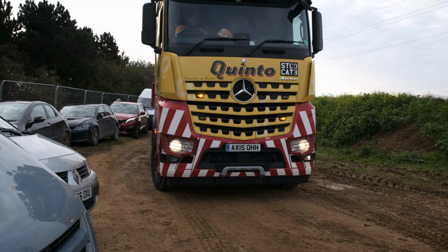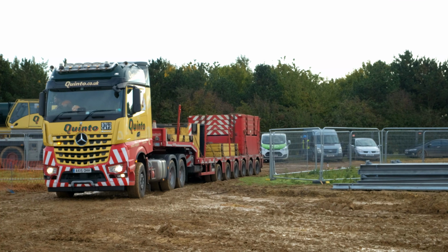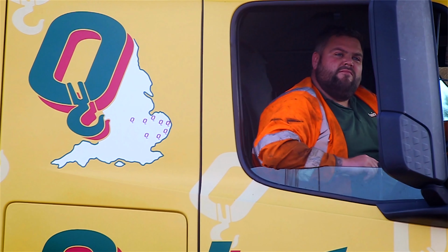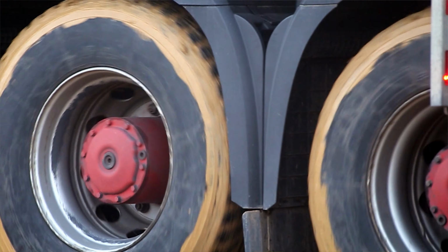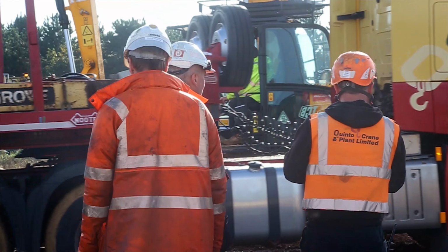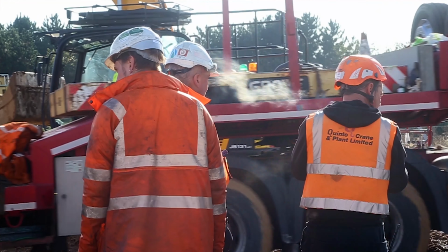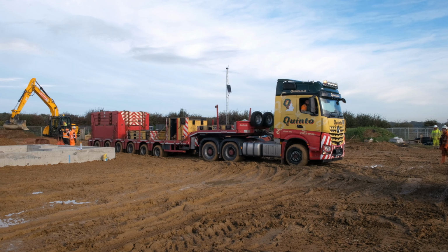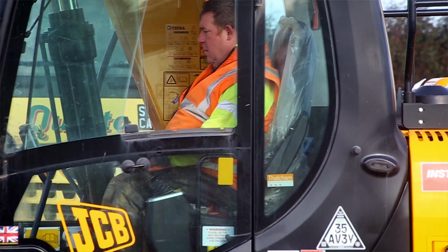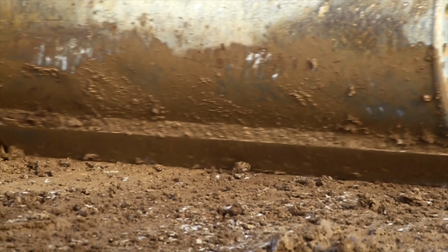We've installed a 300-metre access track from the main road, reinforced by about 450 mil of Type 1 stone. And on top of that, we've crossed over a fuel aviation line which supplies Luton Airport. We've installed a 4 metre by 2 metre concrete slab, approximately 1 metre above the pipe, to give it the necessary support for when the transformer's brought over the pipeline.